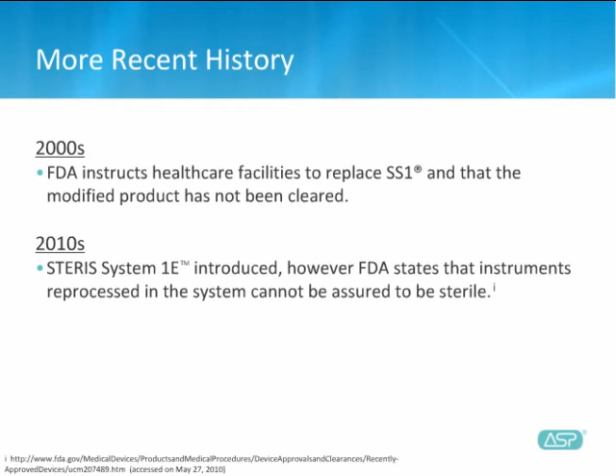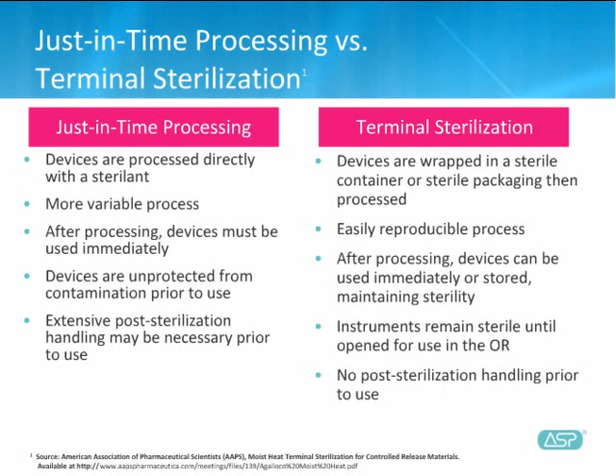Today, we have multiple choices for processing surgical equipment. Let's go through how each works and the best choices for what you need. There are a number of pros and cons to each. For just-in-time processing, devices are processed directly with a sterilant, and after processing, devices must be used immediately or run the risk of recontamination. For terminal sterilization, a key advantage is that devices are wrapped in a sterile container or sterile packaging and then processed, which means after processing, devices can be used immediately or stored, maintaining sterility. This means that it is terminally sterilized and can be done in advance, reducing immediate pre-op prep. Since we know our history, we are not doomed to repeat it, but rather we are made wise.